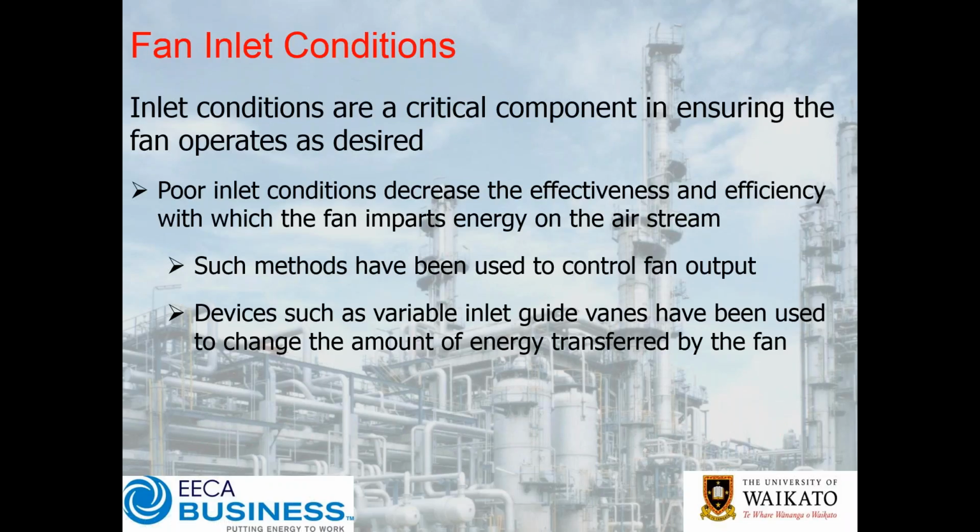Now, the inlet condition to the fan can be very, very important. A poor inlet condition does a couple of things. First of all, it can decrease the effectiveness and the efficiency at which the fan imparts energy to the system. Some of these issues arise from fan control, how you're controlling. For example, you might have variable inlet guide vanes at the front of the fan, which is a little bit better than just having a knife that you slowly pull back.